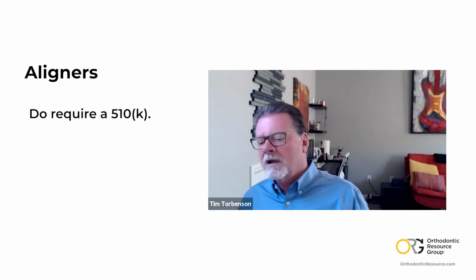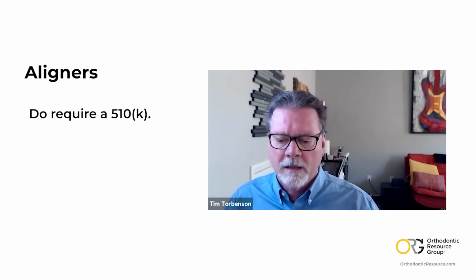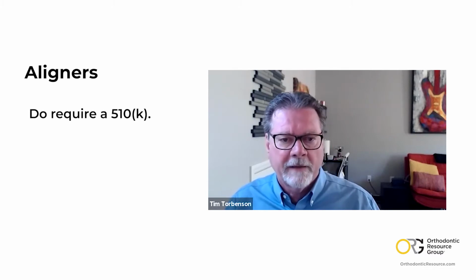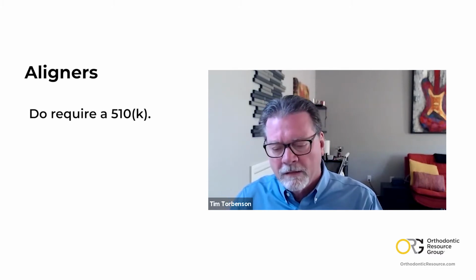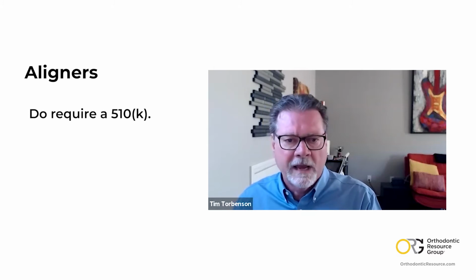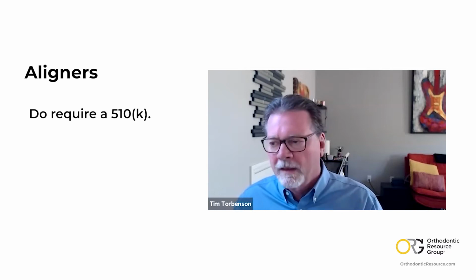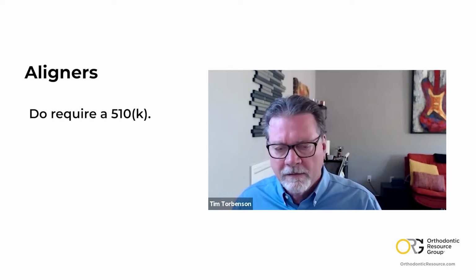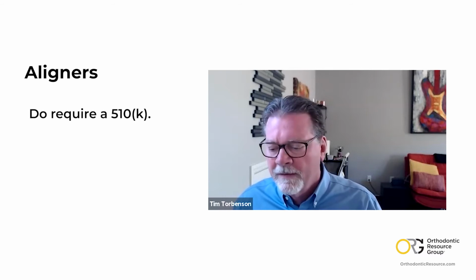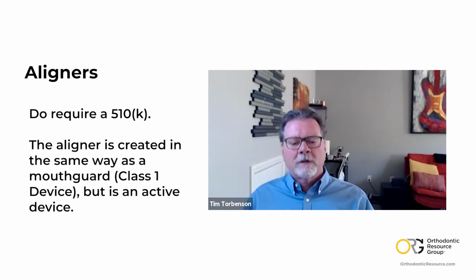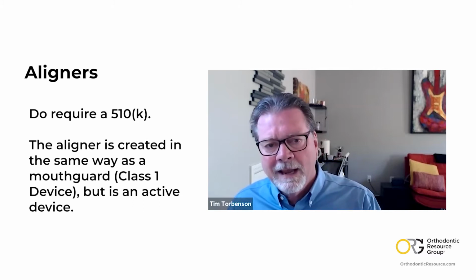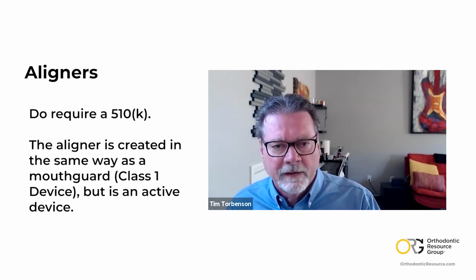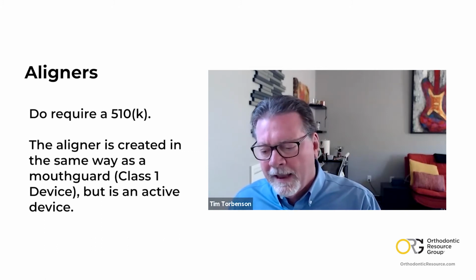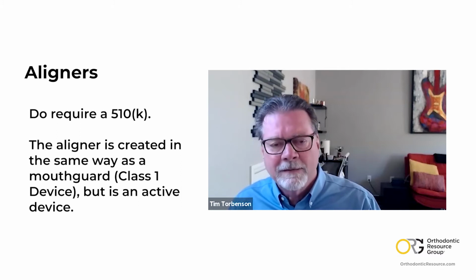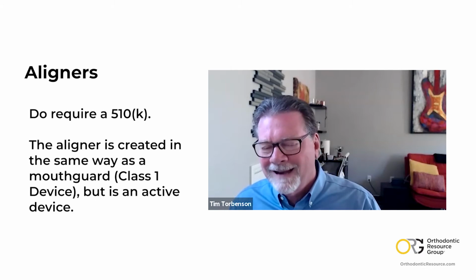We can talk about this in a little different application. If we look at aligners, which do require a 510K, the manufacturing process for the aligner is literally identical to a mouth guard or a retainer, where the post-orthodontic treatment retainer is also thermoformed. Usually it is CAD/CAM designed and delivered to the patient, and it's the same material. The difference between the two, and this is how we have to look at the devices, is that the aligner is an active device. The FDA understands that, using a directional, gentle pressure, it orthodontically moves the teeth. That is an active device.